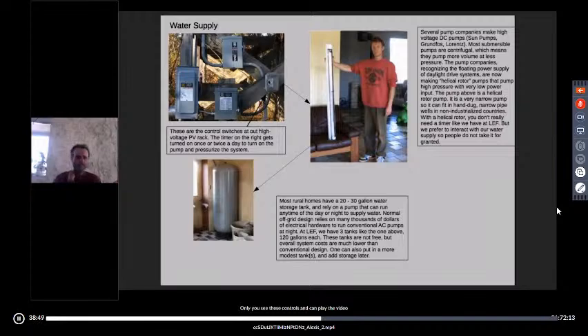You'll notice all of this is in conduit. We wire this as if it were AC equipment, code specified AC style wiring. If you know how to do that kind of wiring, great; if you don't, find somebody who does. It's all grounded, all set up to handle 600 volt AC power by code, even though it's only handling 180 volt DC. Like I said, it can hurt you, it can start fires. Don't mess with this if you don't know what you're doing. But this is how it works.